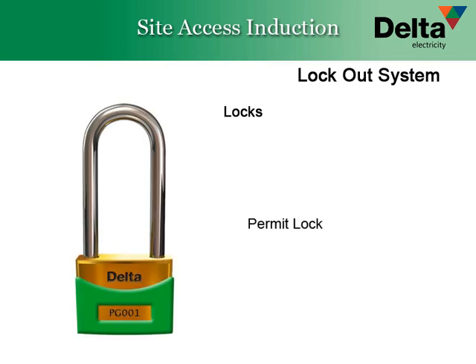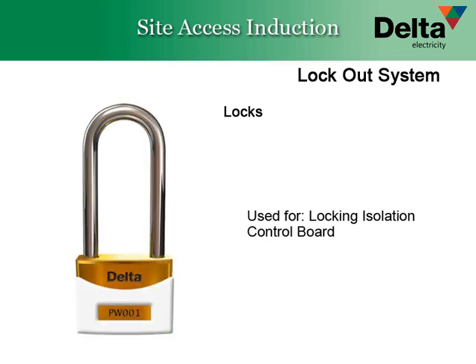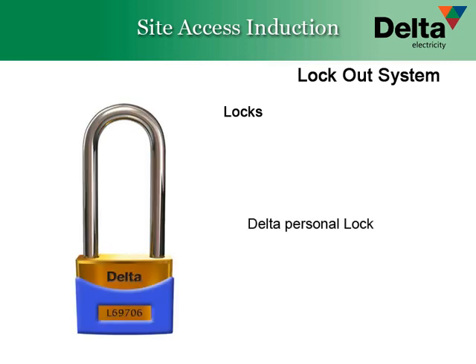Green is the permit lock. White is used to lock the isolation control board. The key to this lock is held by the person in receipt of the permit to work. Blue is the Delta personal lock. One lock is issued to Delta staff that have to work under a permit to work. It has the service number of the person engraved on the lock.